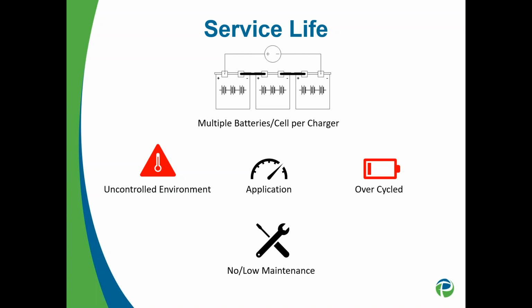And then a lot of times batteries get overcycled with too many discharges - this would be in areas where there are a lot of outages and things like that. But typically what I've seen is they're rarely overcycled too much. You can have the rare instance where they do - you could have sizing issues with the UPS or rectifier system where the UPS can't keep up with the load, and even though it's doing load steps, it can't, so it's pulling on the batteries each time.